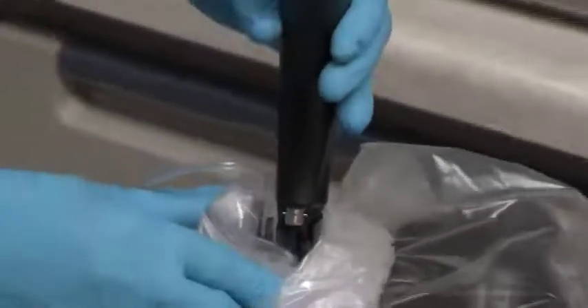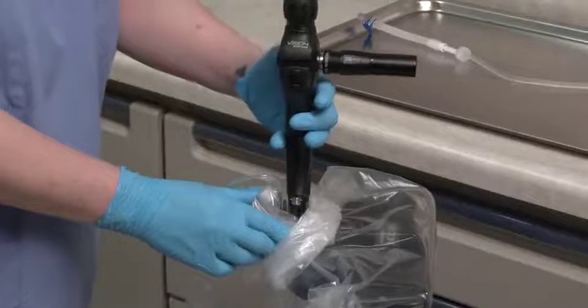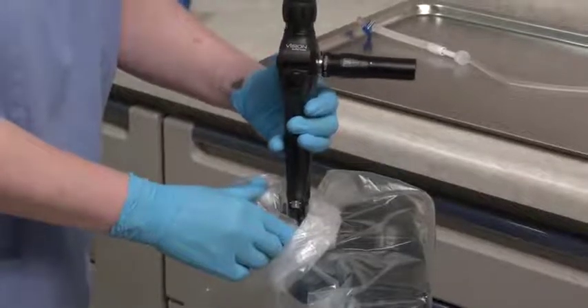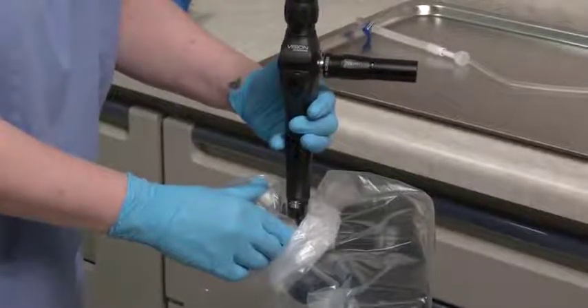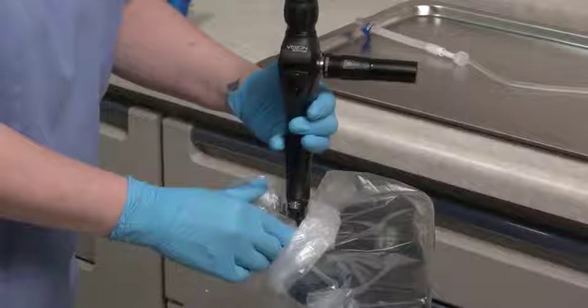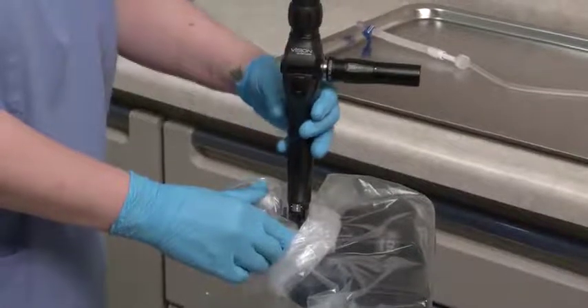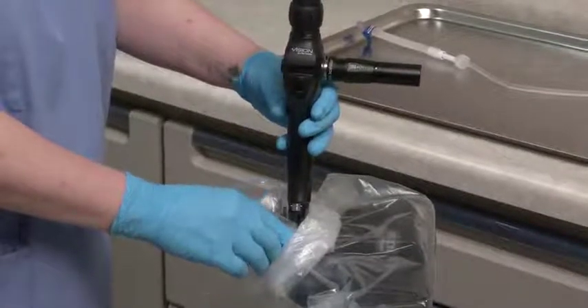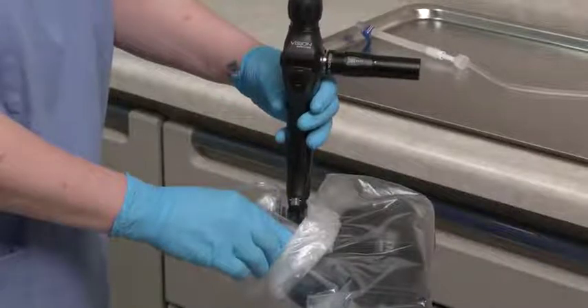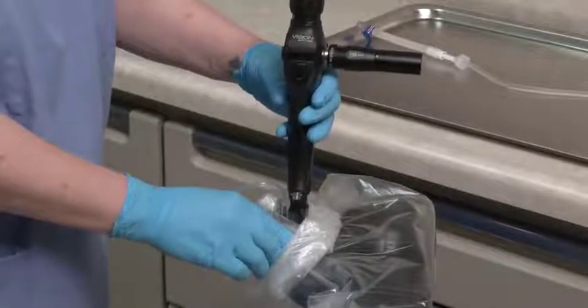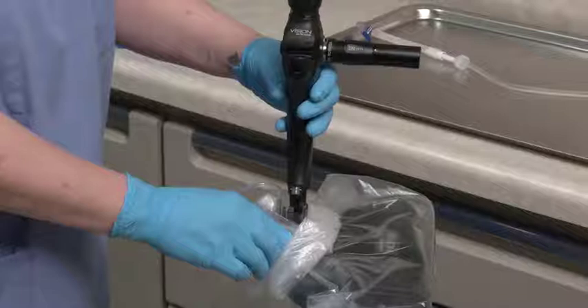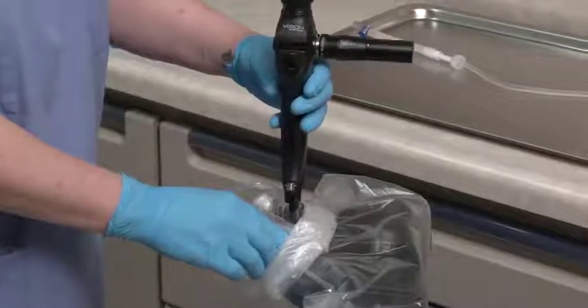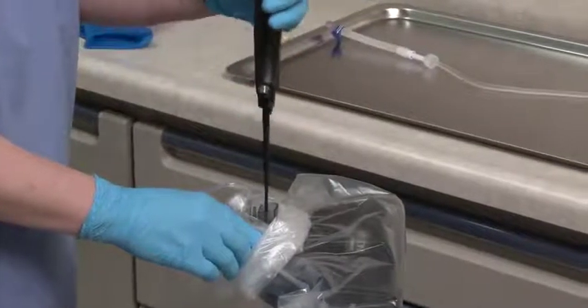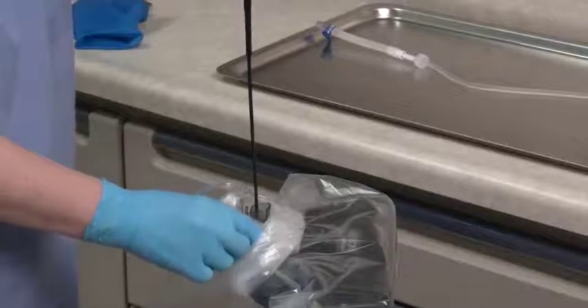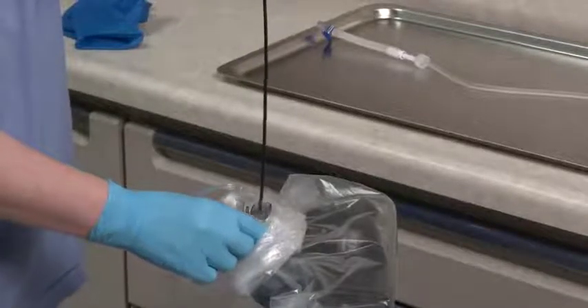Rotate the locking knob into the vertical position so that it is aligned with the slot on the EndoSheath connector. Using the angulation lever, articulate the distal bending section of the endoscope into the straight or neutral position. Hold the endoscope's control body in one hand. Using the bottom outside portion of the drape bag as a barrier between your fingers and the sheath, gently and carefully grasp the sheath window. Then slowly and gently withdraw the scope from the sheath.